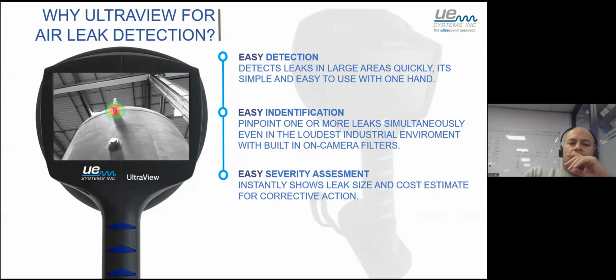So why the camera for leak detection? Of course, there are several technologies for leak detection, but basically you want to do it as fast and as easy as possible. With the camera, detection is easy because you see the leak and know immediately where it is. You see what you scan, which means you can inspect very big areas in a short amount of time. So when you see a hot spot on the screen, you know where to walk to, and then you save the snapshot.